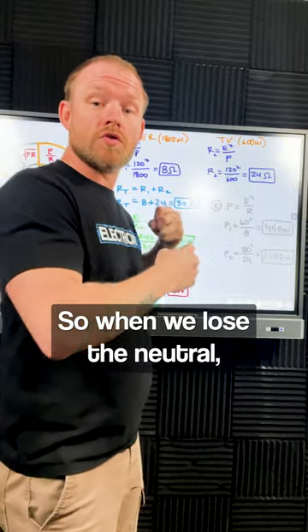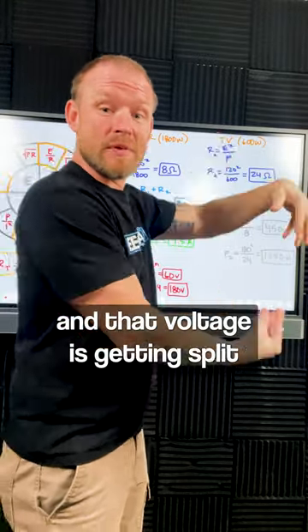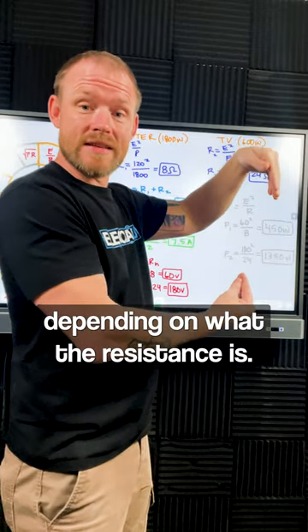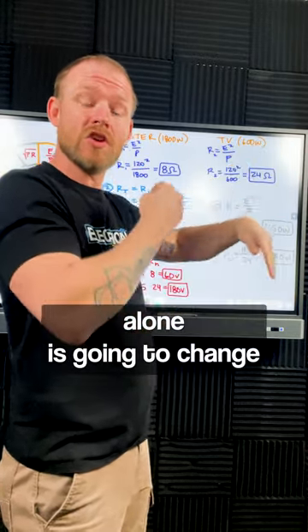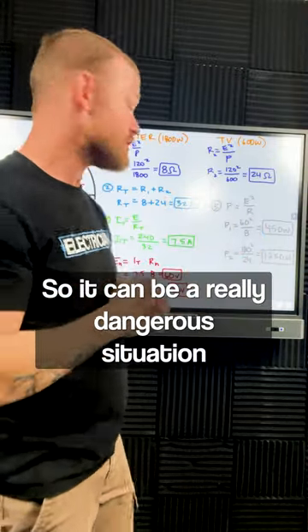So when we lose the neutral, now we have a 240 volt circuit and that voltage is getting split across each one of the loads depending on what the resistance is. The resistance alone is going to change how much voltage is applied to each one of those loads, which can be a really dangerous situation.